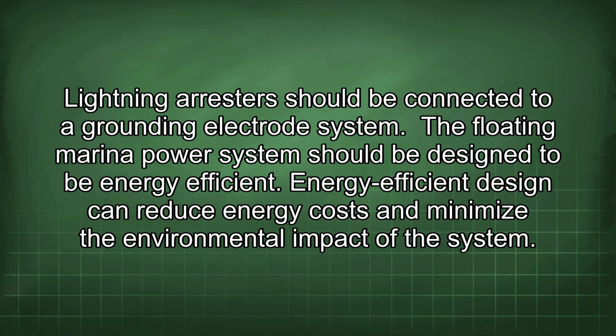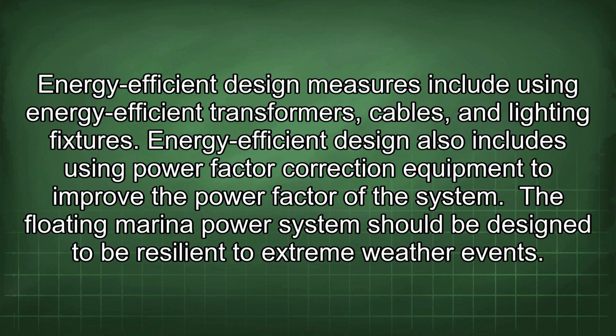The floating marina power system should be designed to be energy efficient. Energy efficient design can reduce energy costs and minimize the environmental impact of the system. Energy-efficient design measures include using energy-efficient transformers, cables, and lighting fixtures. Energy-efficient design also includes using power factor correction equipment to improve the power factor of the system.